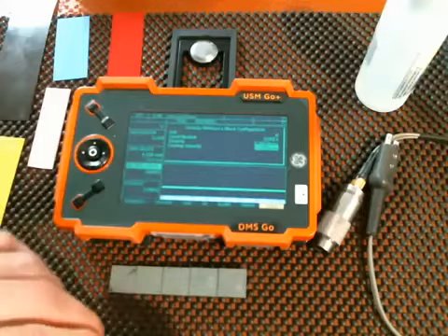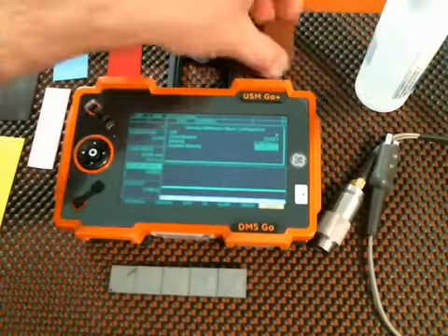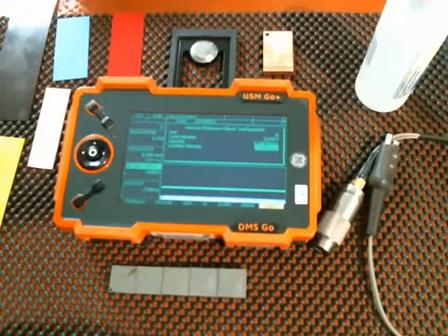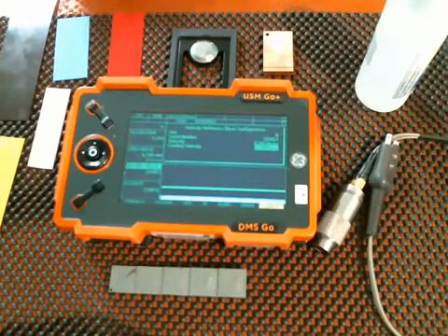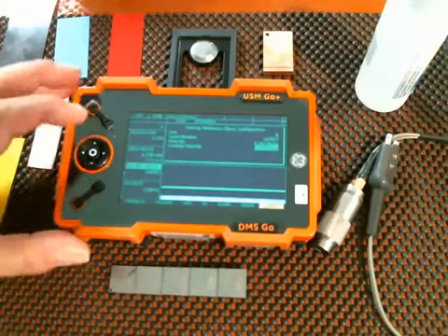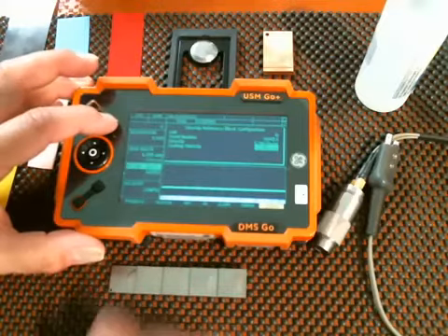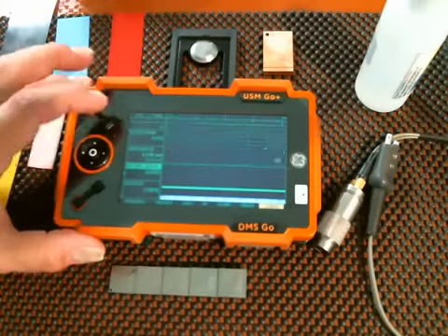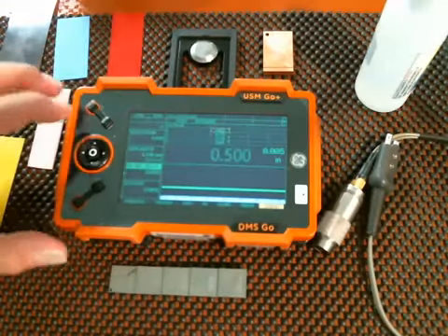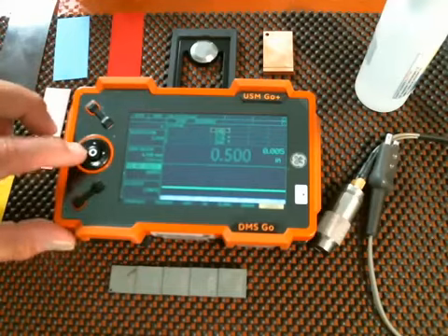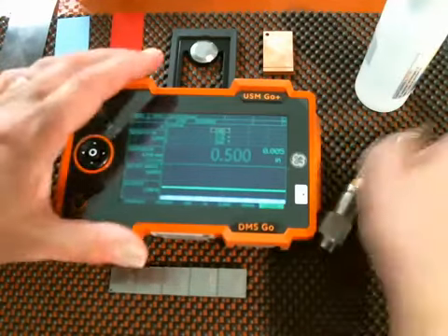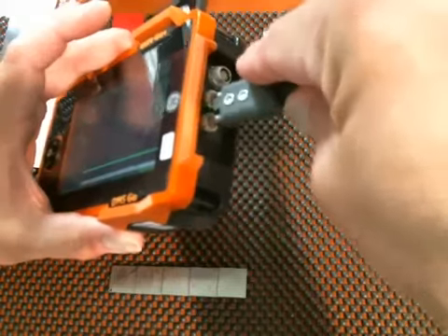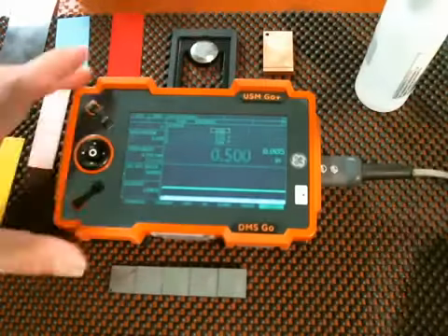So up and down to select, right and left to change the value. And coating velocity is something that you would need to know as a parameter of the paint or coating or epoxy that you expect to encounter when making your measurements. So that needs to be a known quantity that you would enter there. When you've completed setting up the velocity reference block, click the Done key. And at this point, we are ready to connect our probe. So we plug in, making sure to observe the keying on the connector. Go ahead and connect our probe.